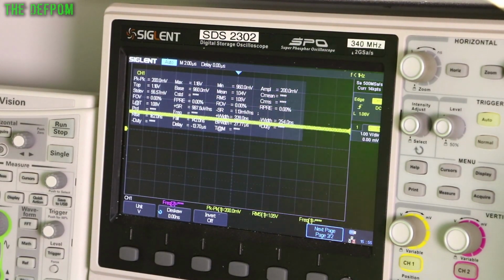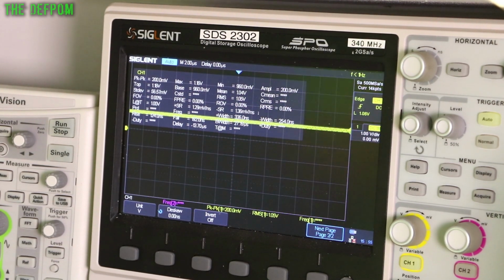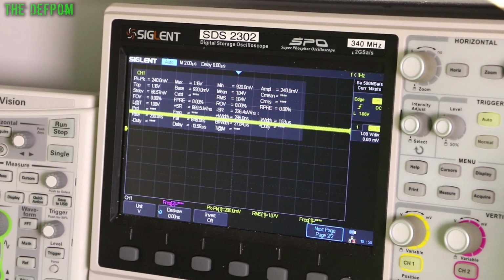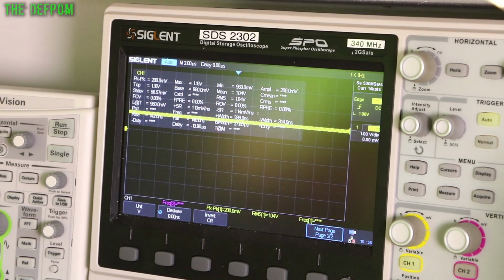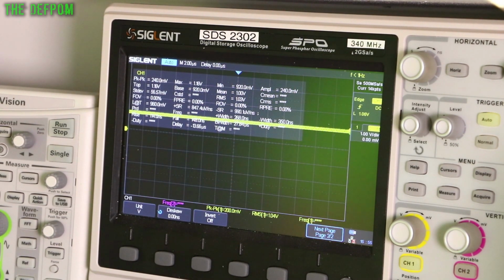So the next step is to measure TP7 and set it to 1.05 volts DC. Now I've got this set up on the scope already. It's already basically there. I've already done this adjustment when I first got this unit because it was wrong because of the line voltage being different and line frequency being different. So it needs to be calibrated to the line frequency. So I've already done this adjustment once. If you go up on the all measure here, you can see the RMS voltage is 1.05.